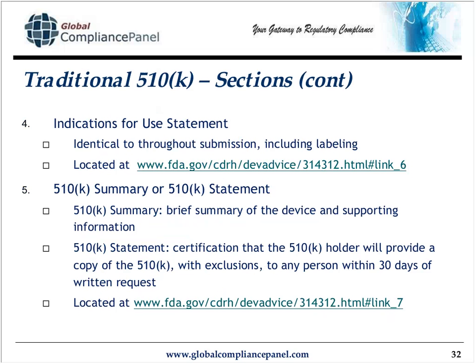Section 4 is the indications for use statement. Here's its location also. Make sure when you populate the indications for use statement that the wording you use is identical throughout the submission, including on your proposed labeling.